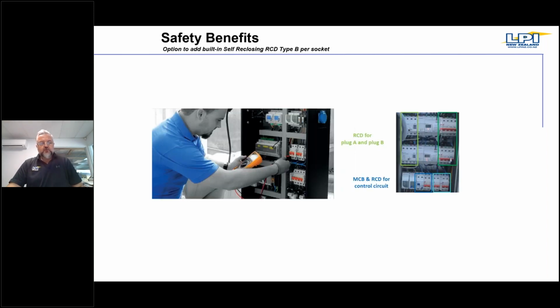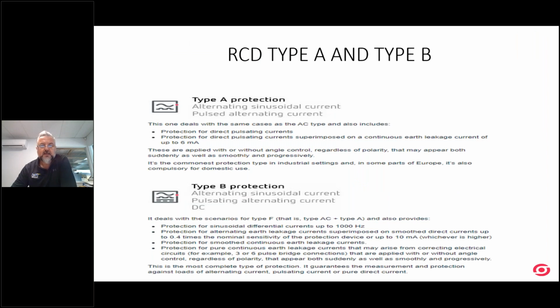Now we're moving on to the more important area, which is safety. There have been lots of discussions on the safety of EV chargers and how they need to be protected, and there are a few different upgrades, what type of RCDs and so on should be used. At this stage, the RCD that has to be used is a type B RCD, and it has to be installed at the point of supply.